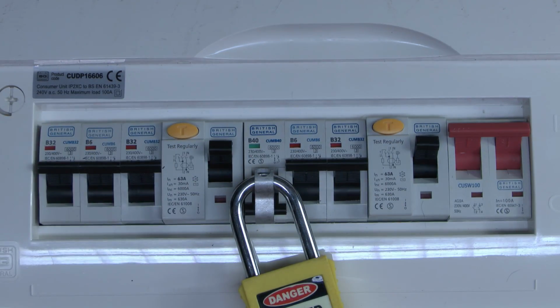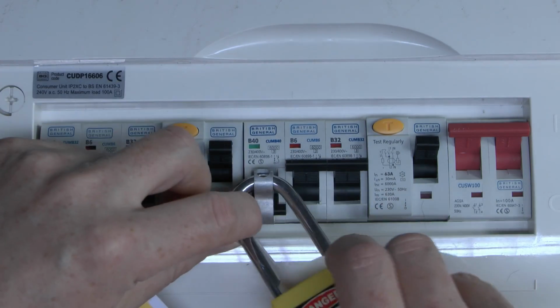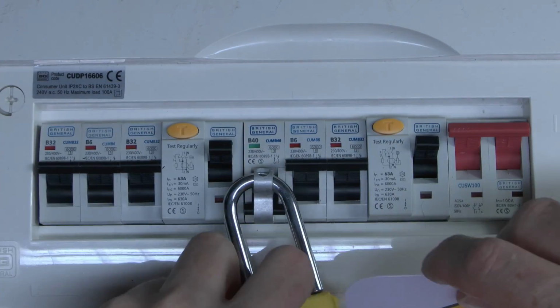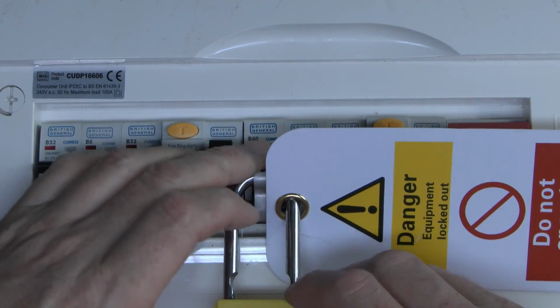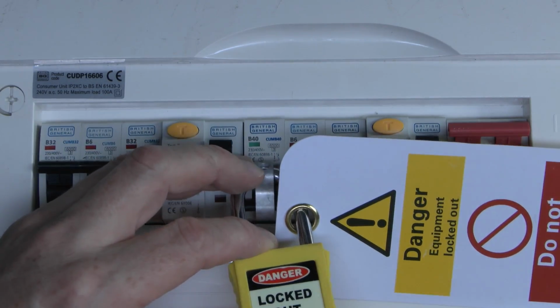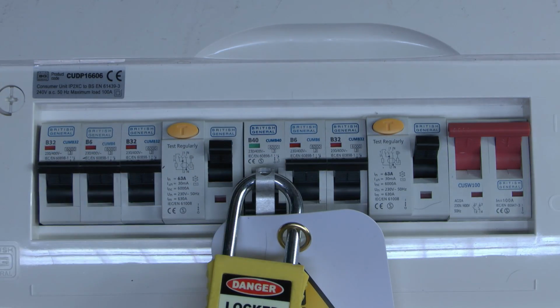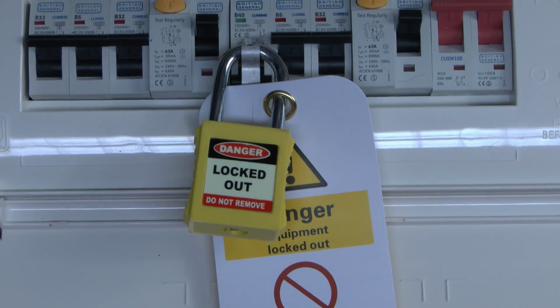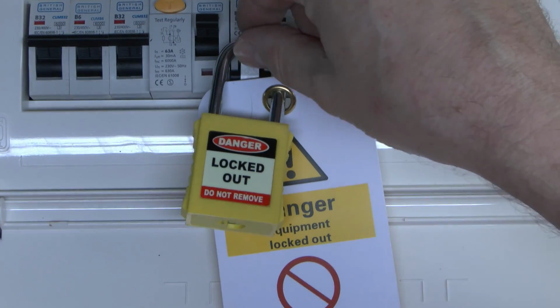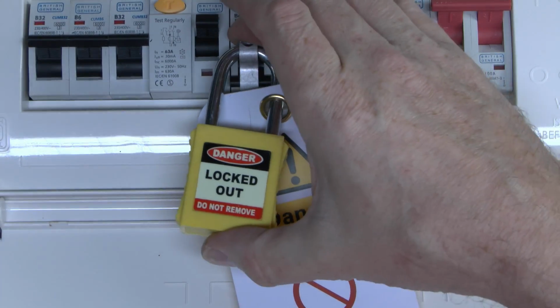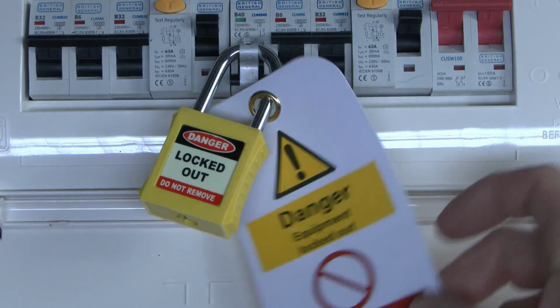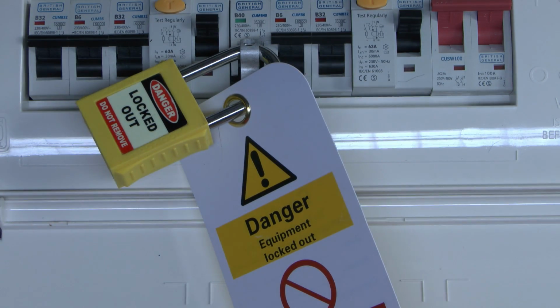The idea of the labels is that you put that around the padlock as well, slide that on, lock it in position. Now you have the actual locked out arrangement, so you can't move the circuit breaker lever, padlock through there to secure it in position, warning notice, and also your large warning notice, making it abundantly obvious to anybody that this has been disconnected and turned off for a reason.